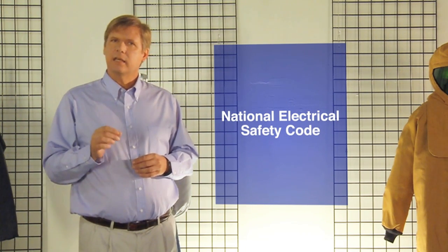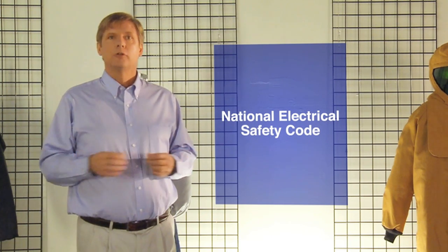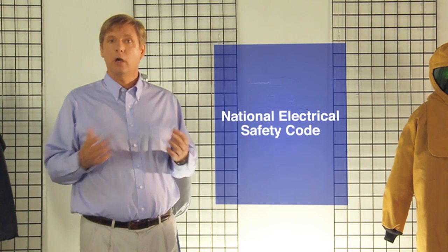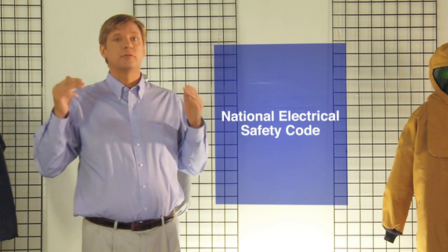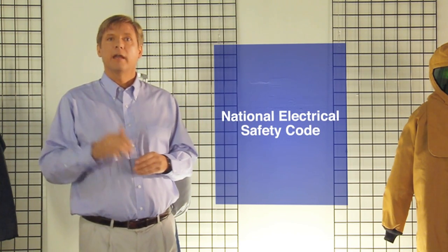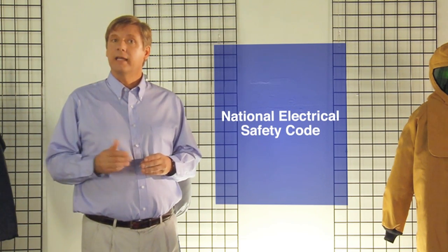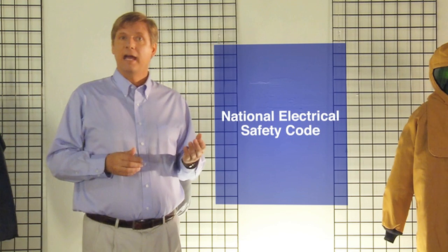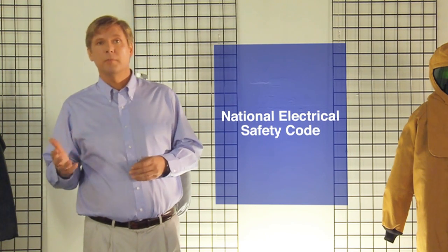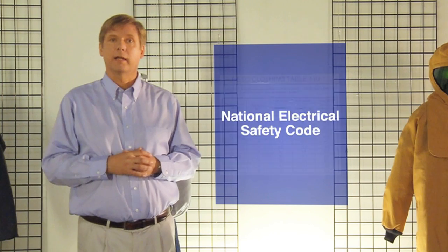In NESC, the utility is required to perform a hazard risk assessment to determine the exposure potential to an arc flash for various work practices. If the hazard is above 2 calories per square centimeter, then arc-resistant clothing must be worn. Just like NFPA 70E, there is an option for either a detailed hazard analysis or simplified tables which can be used to determine the FR clothing and appropriate arc rating.